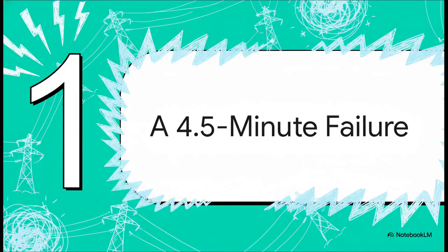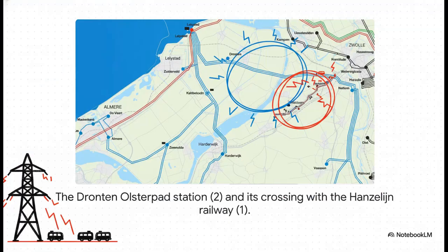All right, to really get a grip on this, let's start by setting the scene on the day of the incident. Okay, so take a look at this map. This is the area in Flevoland. The whole thing kicked off at the brand new Dronten Olsterpad substation. You can see it marked there with a number 2. It was getting its power from a single 150 kilovolt circuit from the main station in Lelystad. Now you're going to want to pay close attention to location number 1. That's where the high voltage line crosses a major railway line, the Hanzelijn. This spot is going to become critically important a little later on.